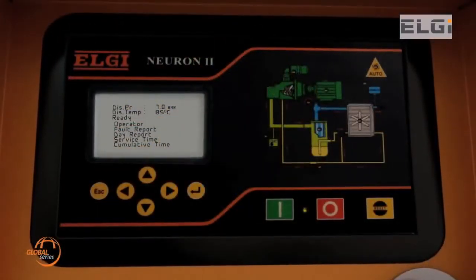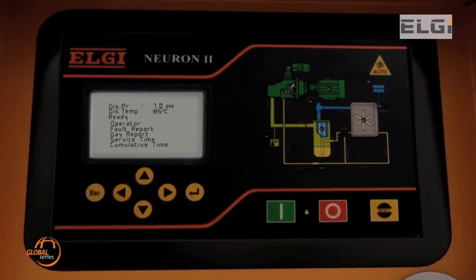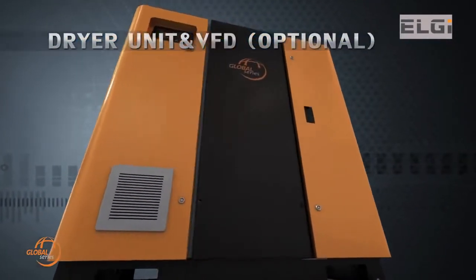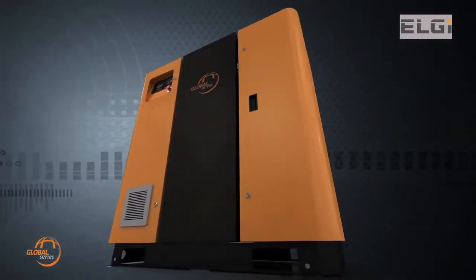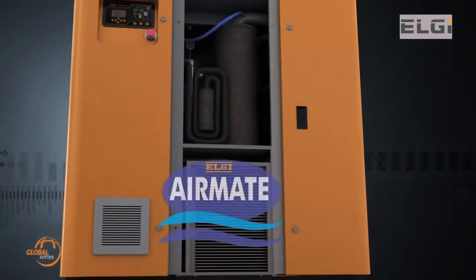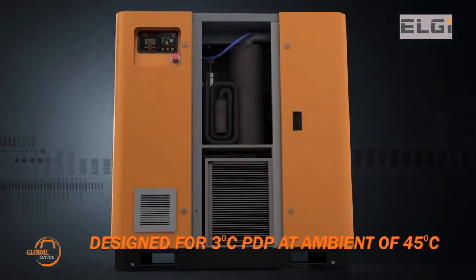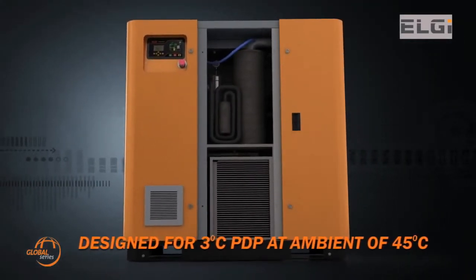The Neuron 2 controller is a dedicated and extremely compact industrial automation controller for control of medium to large-sized screw compressors, custom designed as an advanced embedded control solution. The Global Series also provides customers with the option of inbuilt air treatment for moisture-free air with ELGI's AirMate Refrigerant Air Dryer, which works at high ambient conditions of 45°C and delivers a dew point of 3°C.